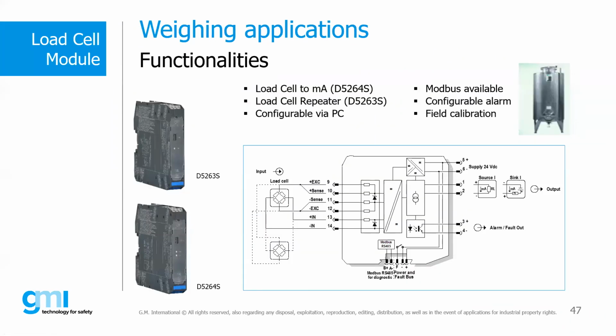In our product range, we also have a solution for weighing applications. A load cell, also called a strain gauge, is used in weighing systems, where you can connect a load cell and convert it to a 4 to 20 milliamp signal. A load cell repeater is used when the system is able to read the load cell directly. Those units are configurable with a PC through Modbus configuration, and also offer alarms and field calibration.